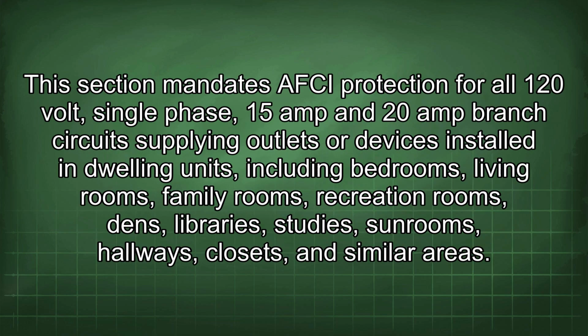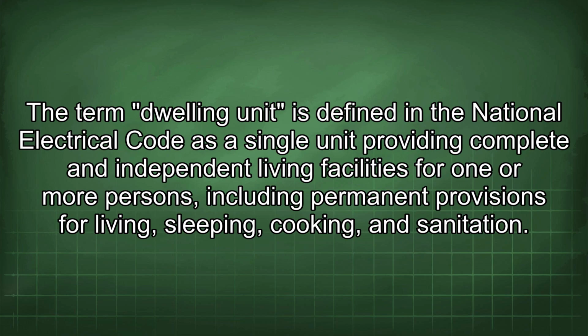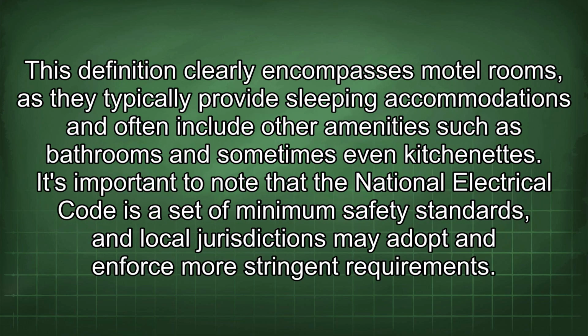This section mandates AFCI protection for all 120-volt, single-phase, 15-amp and 20-amp branch circuits supplying outlets or devices installed in dwelling units, including bedrooms, living rooms, family rooms, recreation rooms, dens, libraries, studies, sunrooms, hallways, closets, and similar areas. The term dwelling unit is defined in the National Electrical Code as a single unit providing complete and independent living facilities for one or more persons, including permanent provisions for living, sleeping, cooking, and sanitation.